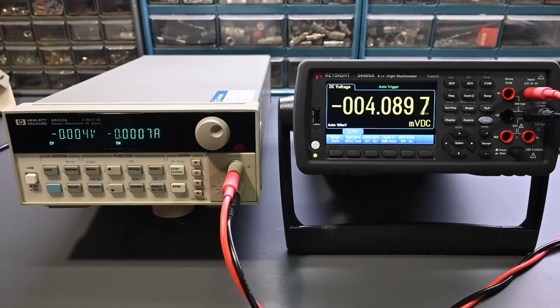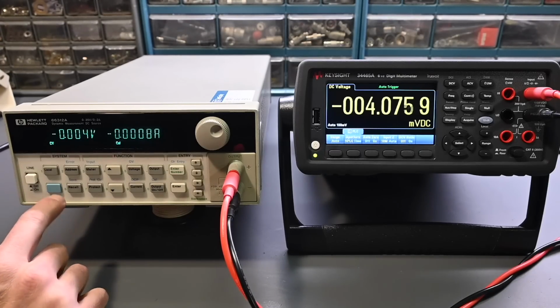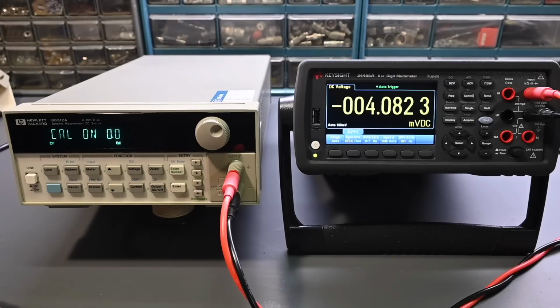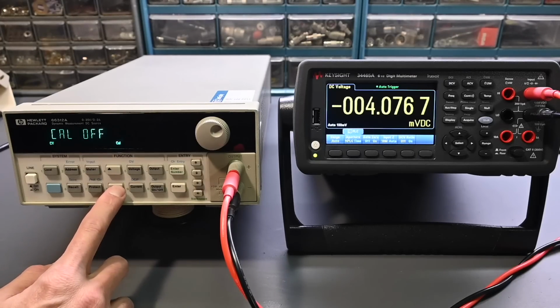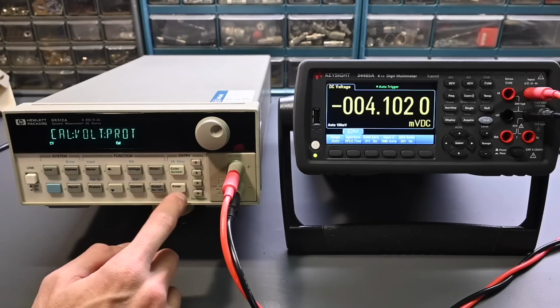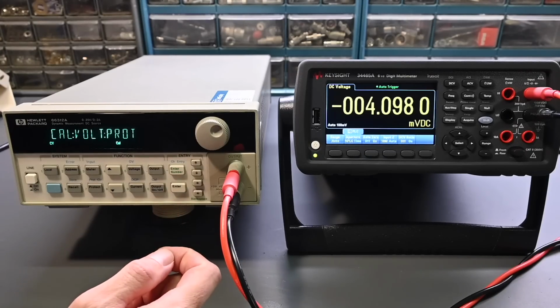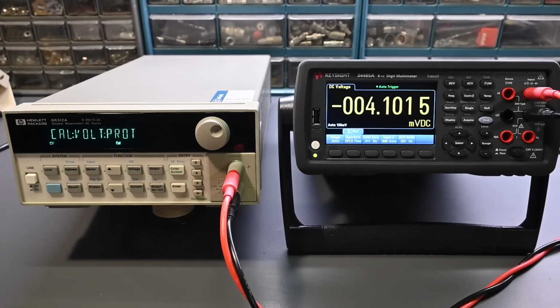Okay, so that's everything for the voltage programming and calibration part. Next is the over voltage protection calibration. It says press Shift Cal. Scroll to Cal voltage protect. Right there. Press enter. And then it says, when you press enter, wait for the DC source to compute the over voltage calibration constant. The display returns to the meter mode when the calculation is complete. All right, so it says wait. All right, easy enough. So that's completed.